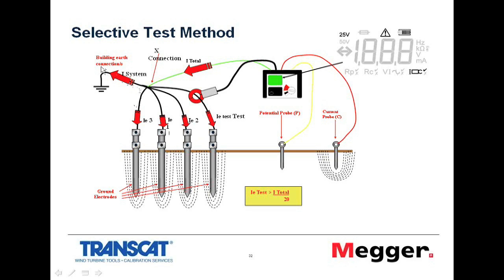any other path to ground, be it another electrode, a connection to another mat or plate, or indeed the building earth connections. Now, in this method, the test current is being split between all those different connection points, but I'm using a clamp to measure just the test current flowing down the electrode I wish to test. So I'm able to take a measurement of that single electrode without making that disconnection, which has the advantage of not having to undo potentially corroded nuts and bolts on clamps, and the time aspect involved. It has a number of benefits.